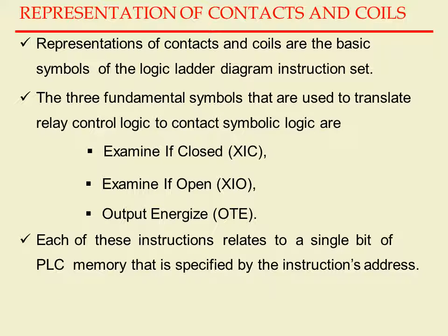Representations of contacts and coils are the basic symbols of the logic ladder diagram instruction set. The three fundamental symbols that are used to translate relay control logic to contact symbolic logic are examine if closed, that is XIC, examine if open, that is XIO, and output energize, OTE. Each of these instructions relates to a single bit of PLC memory that is specified by the instruction's address.